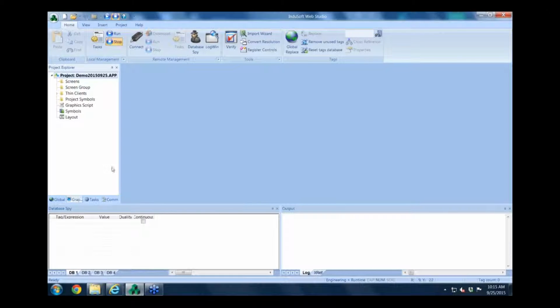The first thing you want to do is go to your Communication tab and select one of many drivers, the driver which applies to the device you're talking to. For this example, I'll use Modbus TCP, but you can just as easily use Modbus RTU or OPC as well to connect to our devices. Depending on which device you choose, you need to select the appropriate driver or communication method for communicating to it.